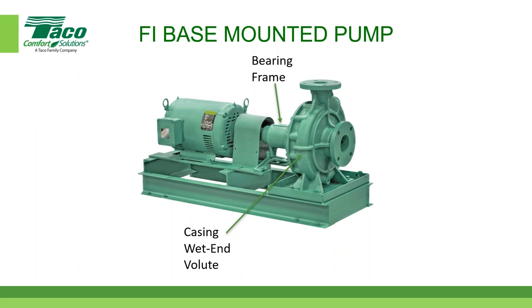Bearing frame, very, very important. And that's what connects on a base-mounted pump that's split-coupled, like this one is, and I'll define that in a second. The bearing frame connects the impeller through a shaft, and then on the other end, it has a coupling, and then another coupling on the motor shaft. Okay, so the bearing frame has two bearings in it, and we're going to get into the details of the Taco bearing frame and how it's made very shortly. And then there's also, on ours and probably on other manufacturers, a bearing frame foot support. You can kind of see it right here. That just supports that bearing frame.